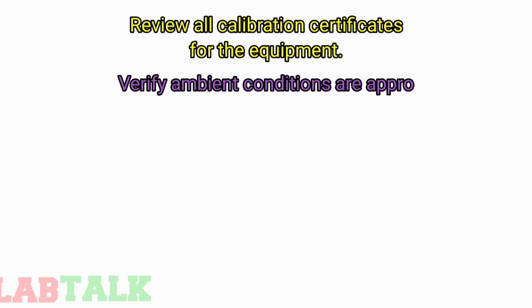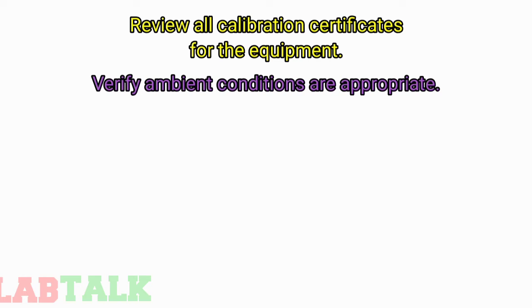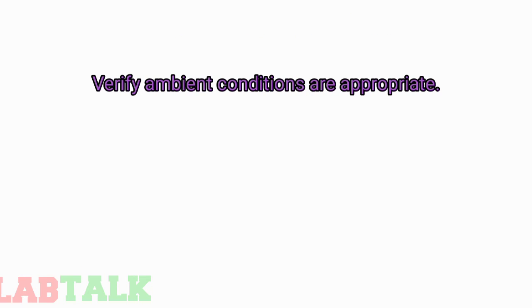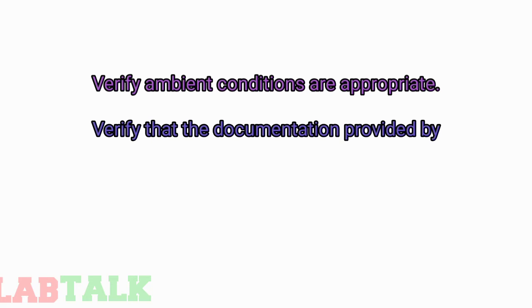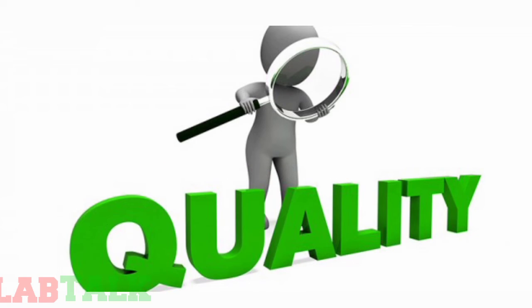Verify that the ambient conditions are appropriate for the operation of the equipment. Verify that the documentation provided by the manufacturer will allow maintenance of the system. Record any deviation to the system equipment. Prepare a deviation report including justification and impact on the function. Prepare an IQ report and submit the report for review and approval to the Quality Assurance Committee.